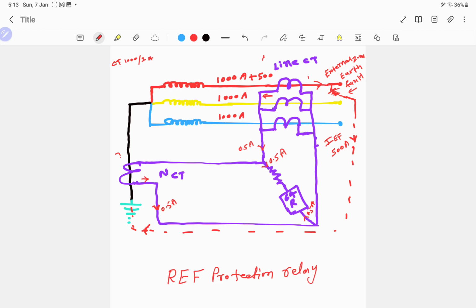So assume there is a fault on the red phase, and it's shorted with the earth somewhere, so that the earth current will flow from the red phase at the shorting point, to the earth through the ground towards the source of the fault current. So it will flow from here through the neutral CT into the winding, through the red winding. It will pass through the R phase CT.